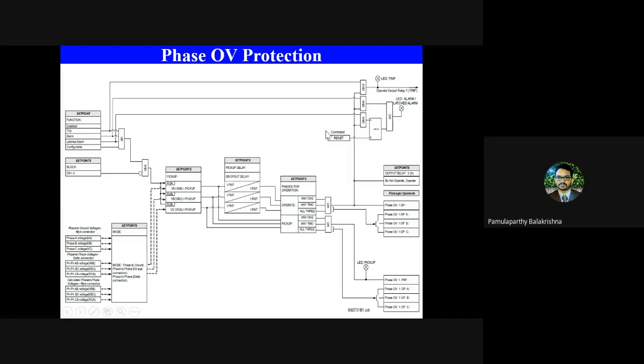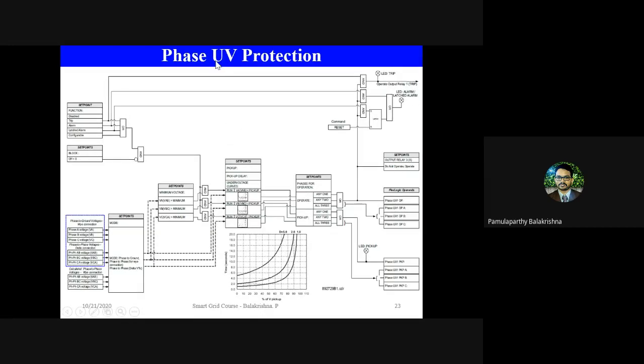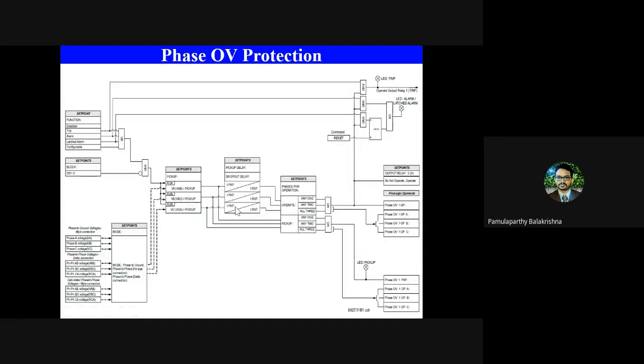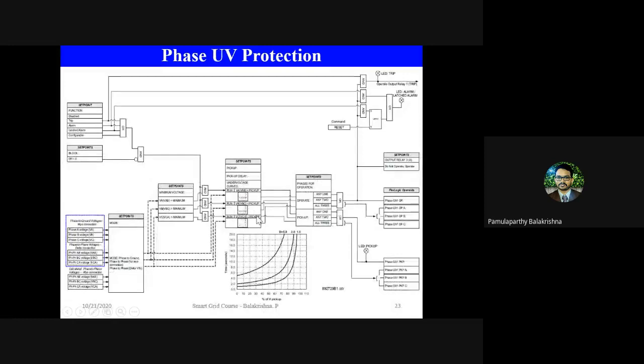So this is how a digital logic design is designed in the field, and it is common for everything. For example, this is overvoltage. If you take the undervoltage function, the only difference is that the voltage coming in is the same, and here you are checking whether an undervoltage condition exists or not. For the undervoltage function, another way of executing the logic is that here you have a fixed timer. The user will configure the fixed timer, or it will adjust adaptively based on the situation.